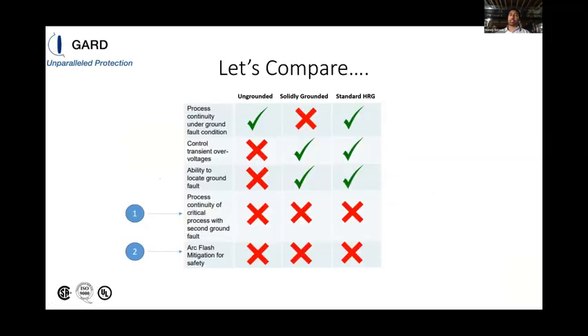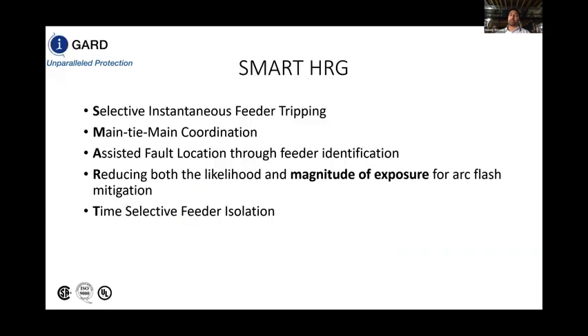So far, our standard HRG offering takes the majority of the advantages of ungrounded and solidly grounded systems while eliminating the majority of the disadvantages. The only thing that we're missing is process continuity in the event of a second ground fault condition, as well as arc flash mitigation for safety. So Smart HRG is where we can make this step.